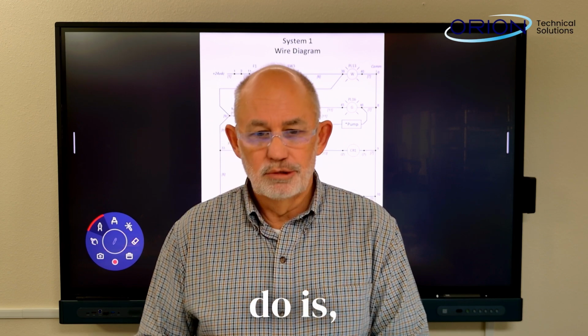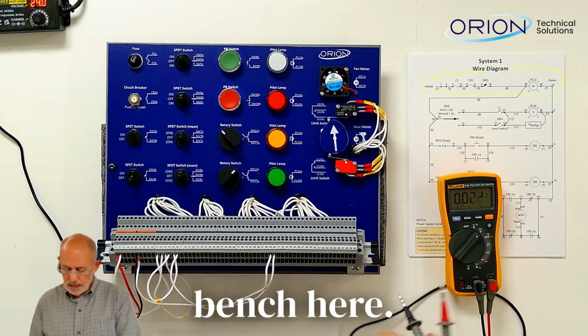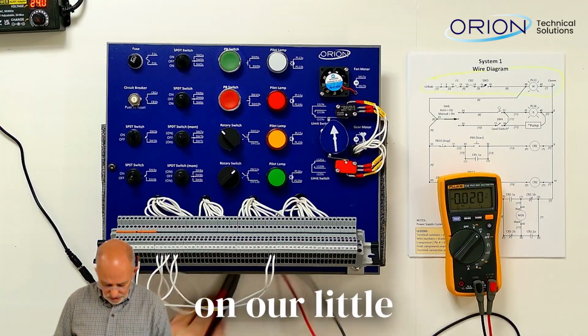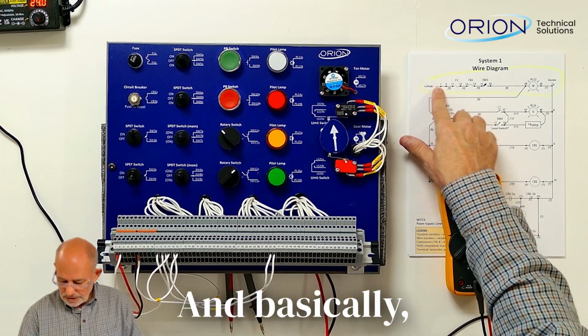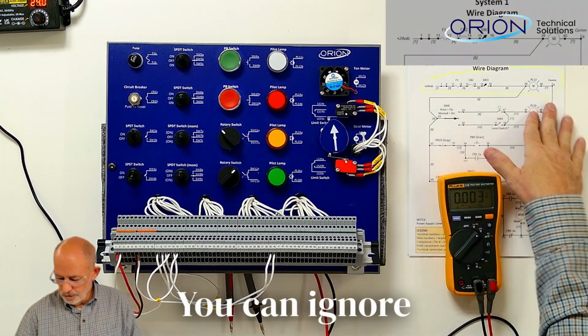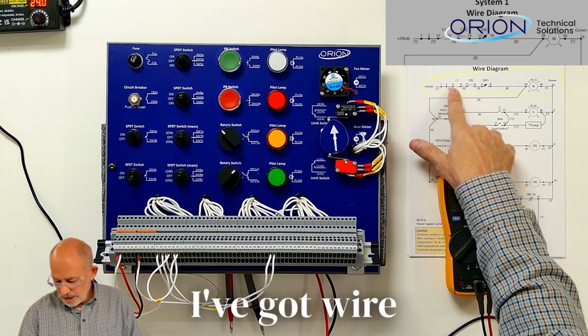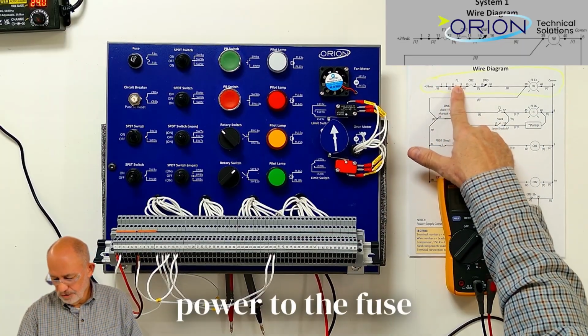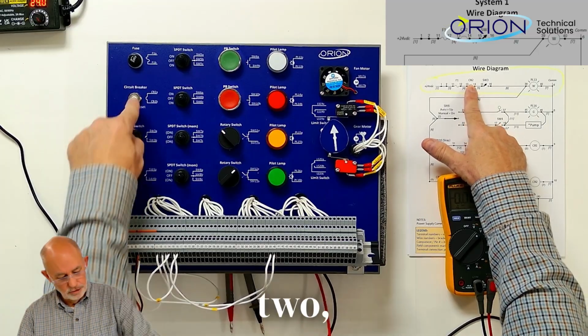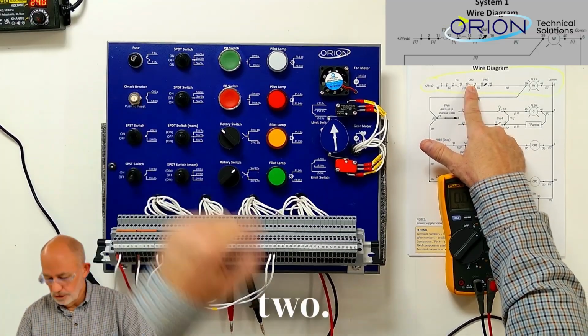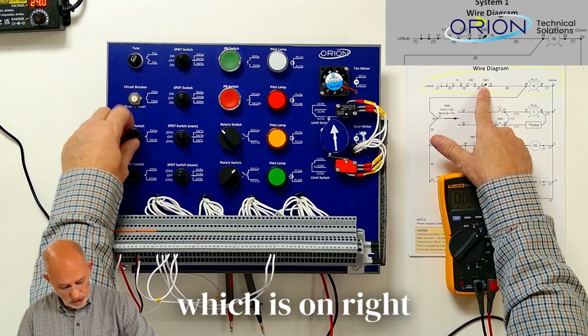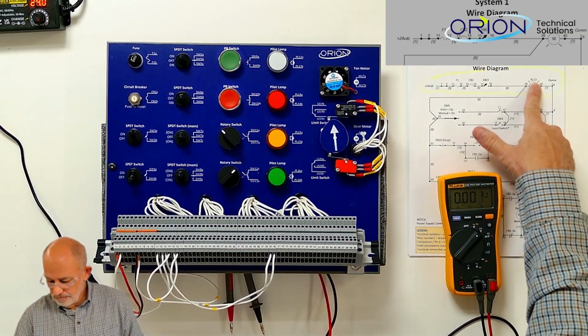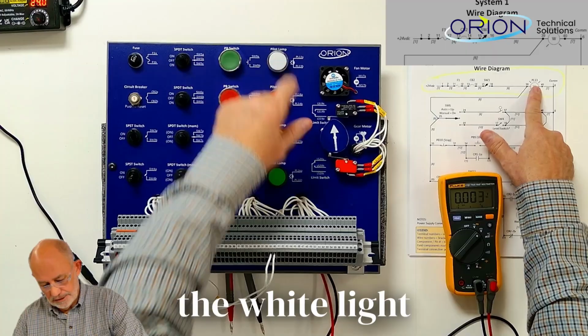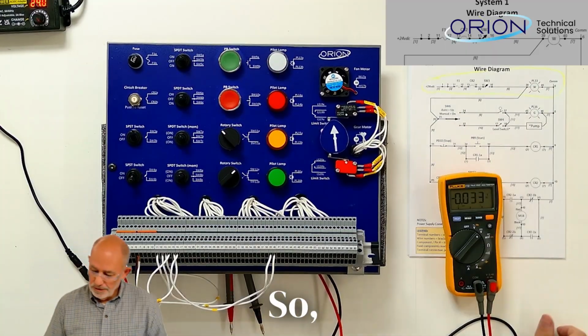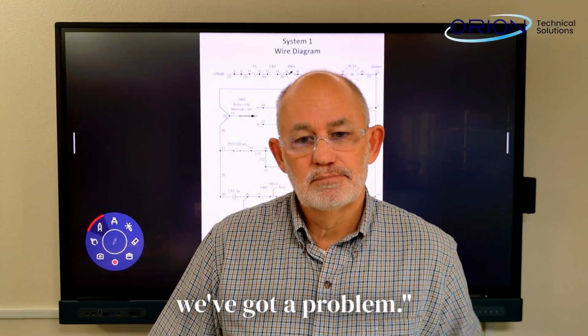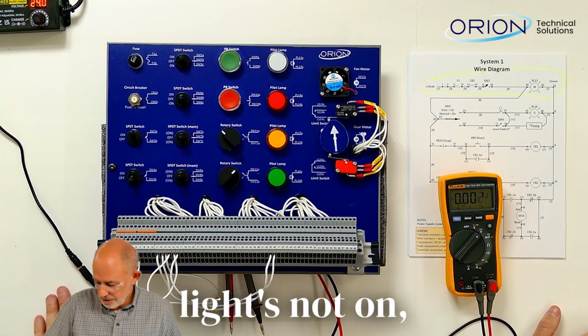So what I'm going to do is look at my white bench here. I have a circuit on our little trainers. And basically what I've wired is this top rung. You can ignore the rest. But if you look, I've got wire coming through, power to the fuse 1. It goes through circuit breaker 2, so there's fuse 1, circuit breaker 2. And then it goes to switch 3, which is on right now. But this PL13, the white light, is not on. It should be. So they call and say, hey, we've got a problem. The power's available, light's not on, whatever.